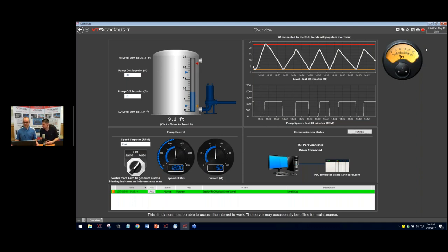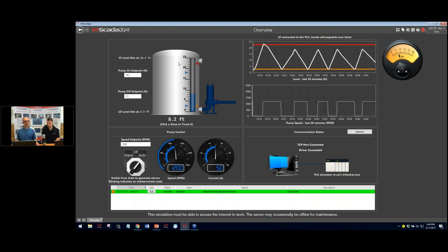So what you'll be looking at is the gauge showing the tag scaled value of 0 to 25 feet, and it's also showing the units. All of that was picked up automatically from the widget, pulling the information from the tag. There are even links to alarms and other things built into the tag, which could change how the widget looks without any extra configuration.